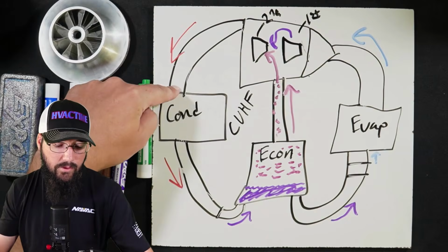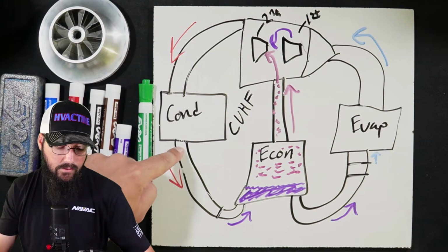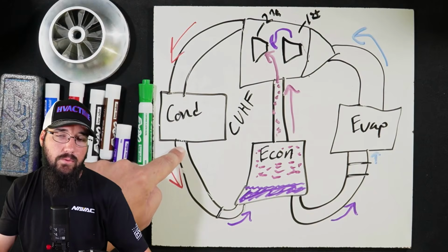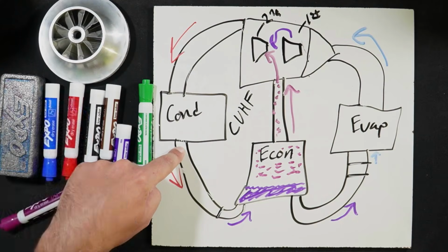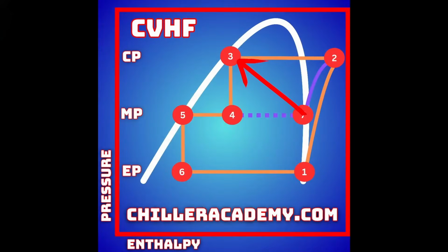So this would be point number 2. We go through the condenser, we're at point number 3. That is when we're going from a hot gas into a liquid right here. So we're at the liquid side of this curve. This is our gas side, this is our liquid side. Everything in between is an intermediate state. We're between a vapor and liquid. So at number 3, we're leaving the condenser and we hit that first flash plate going into the economizer, and we have a split right here.